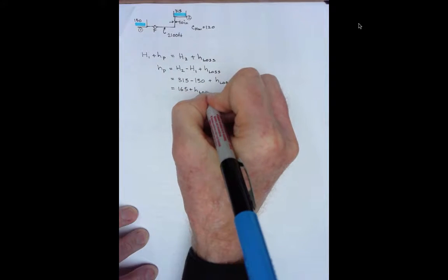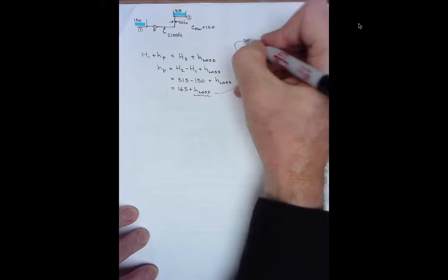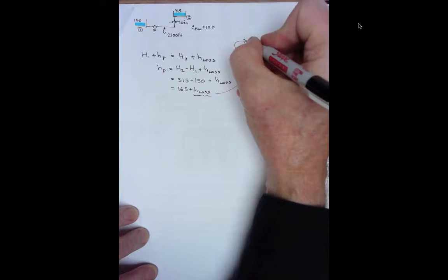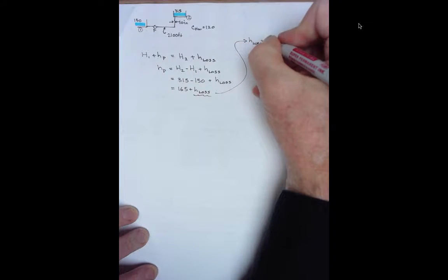In discharge form, head loss using the Hazen-Williams model is 3.02 times the length times the diameter to the minus 1.167 multiplied by the quantity 4 times the discharge divided by pi times the diameter squared times the Hazen-Williams coefficient, all raised to the 1.85 power.